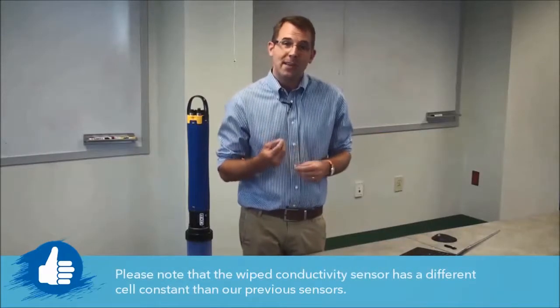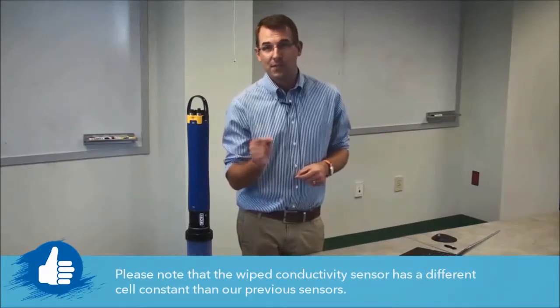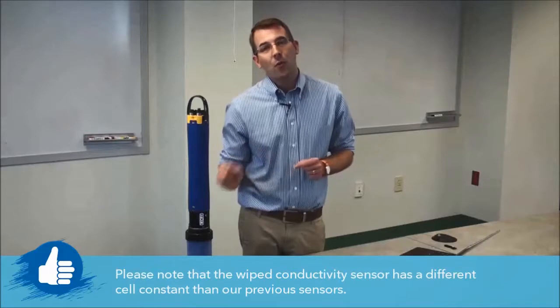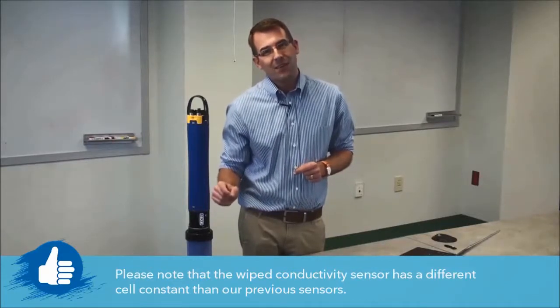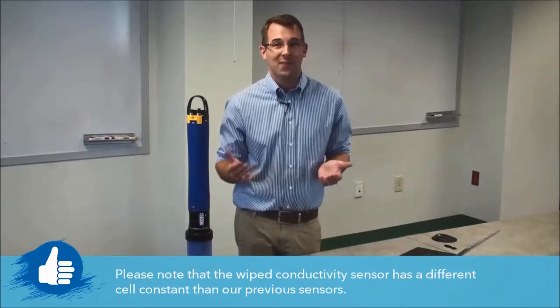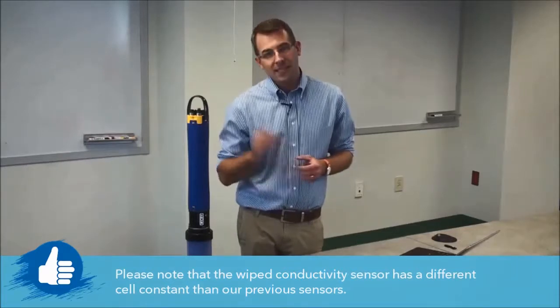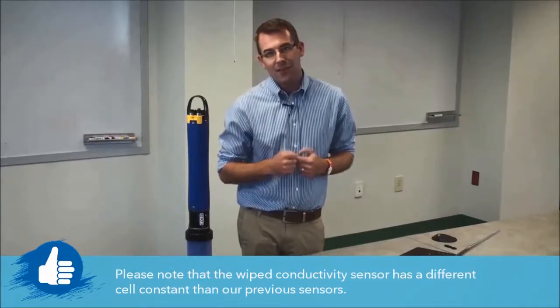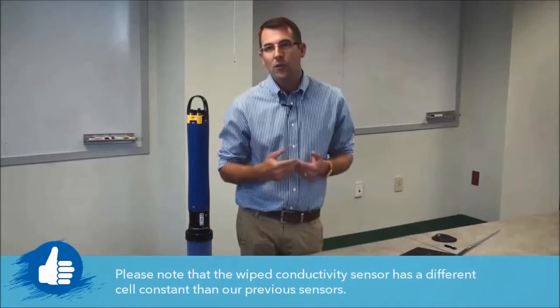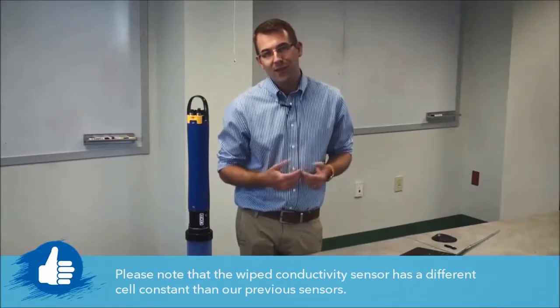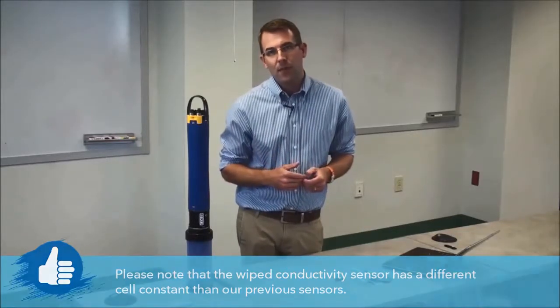An important note is when you're finished with your calibration, you want to pay attention to the cell constant, like you've always done. And you'll note that the wipe conductivity cell constant is nominally 0.47, unlike the black tip CT probe, which had a cell constant of nominally 5.1, or the original CT probe, which had a cell constant of 5.5.